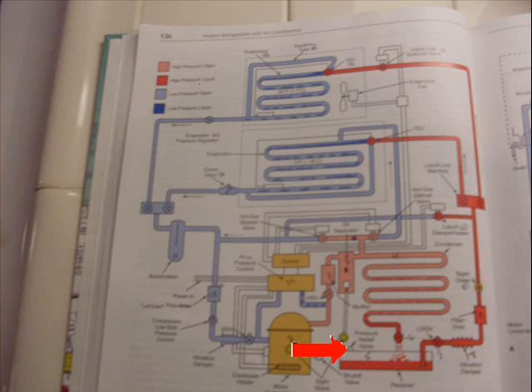The receiver tank has a small little part called a PRV. It's a pressure relief valve. There are three types of pressure relief valves. One is made out of solder. It blows one time when the pressure or temperature gets too hot. Another type of pressure relief valve is a carbon disc. It blows at about 17, 16 pounds, found on chillers. It allows all refrigerant to blow out of the chiller.